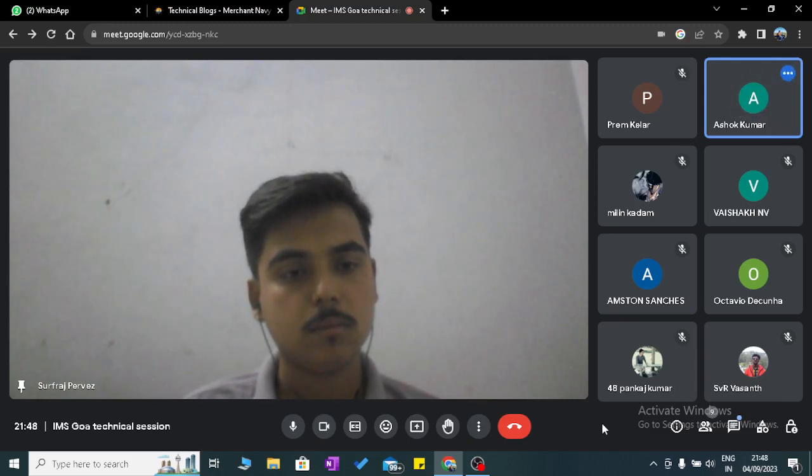fluid moves circumferentially throughout the casing. The area of the casing gradually increases toward the discharge side, so according to the equation of continuity, area increases, velocity decreases. If the velocity decreases, kinetic energy decreases, so pressure energy increases according to Bernoulli's theorem, toward the discharge side. This was my answer. Am I right? Yeah, you are.